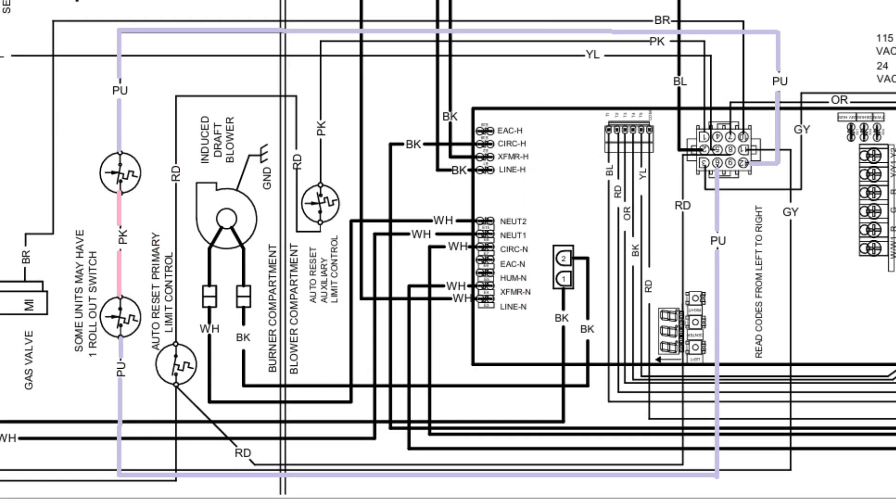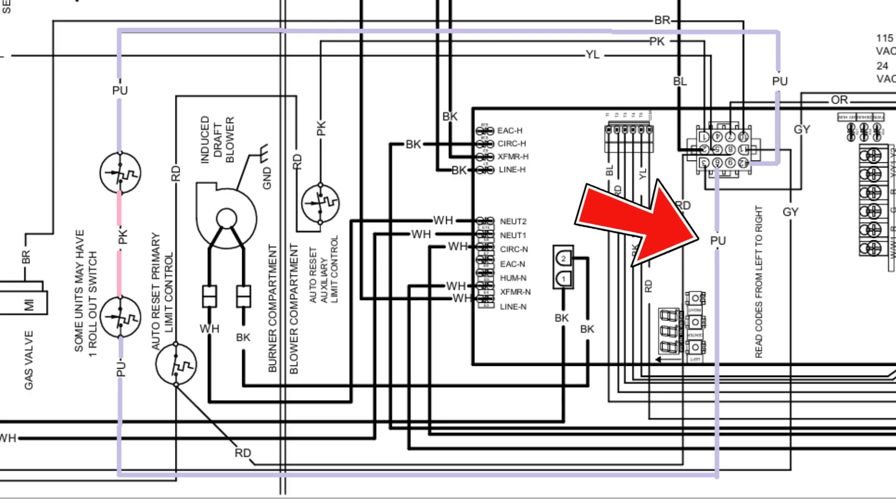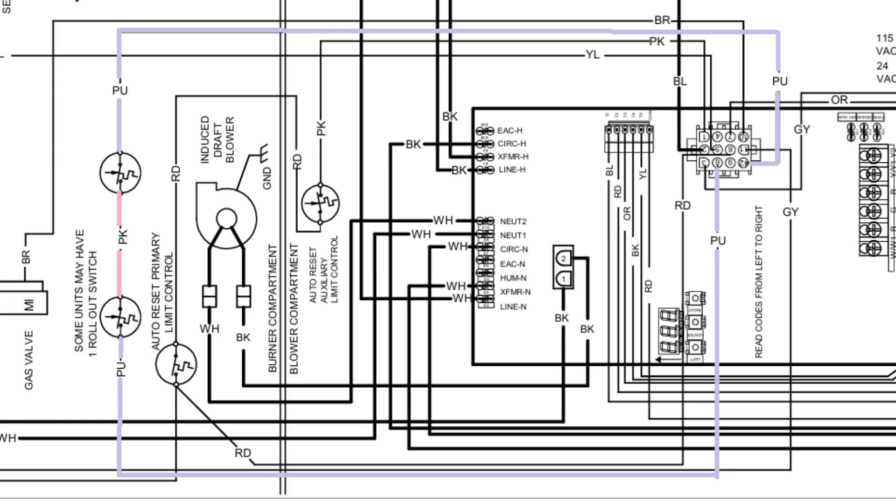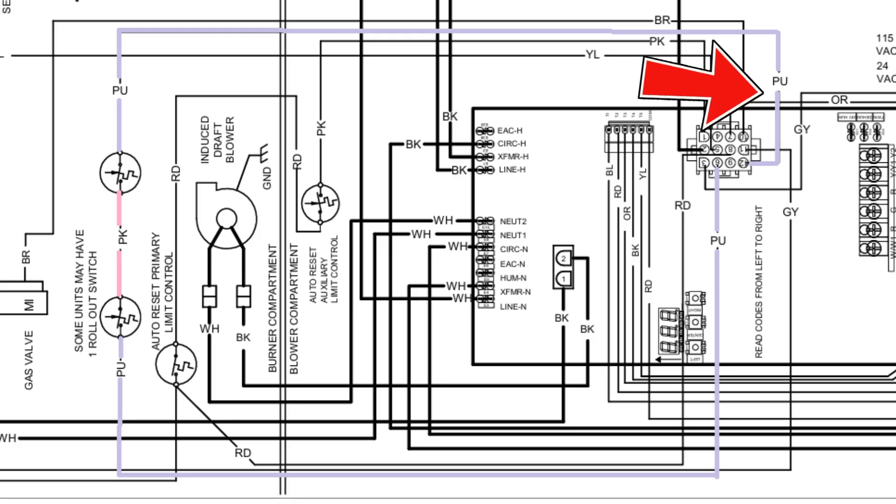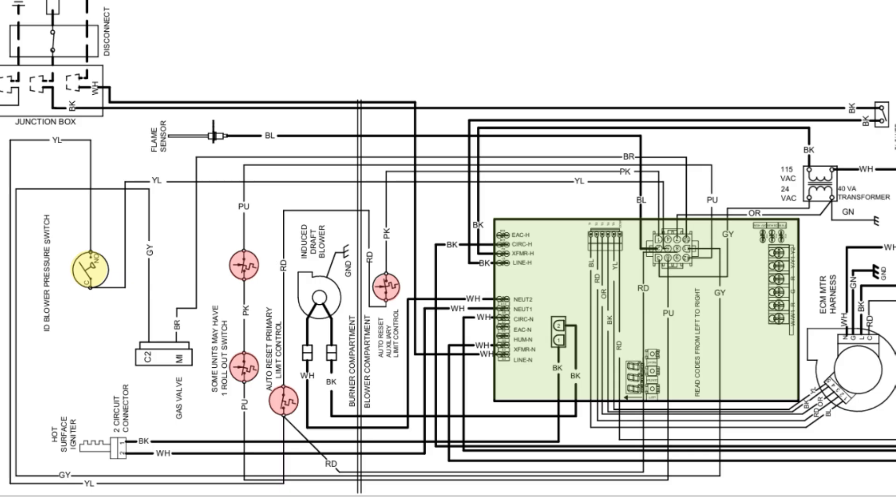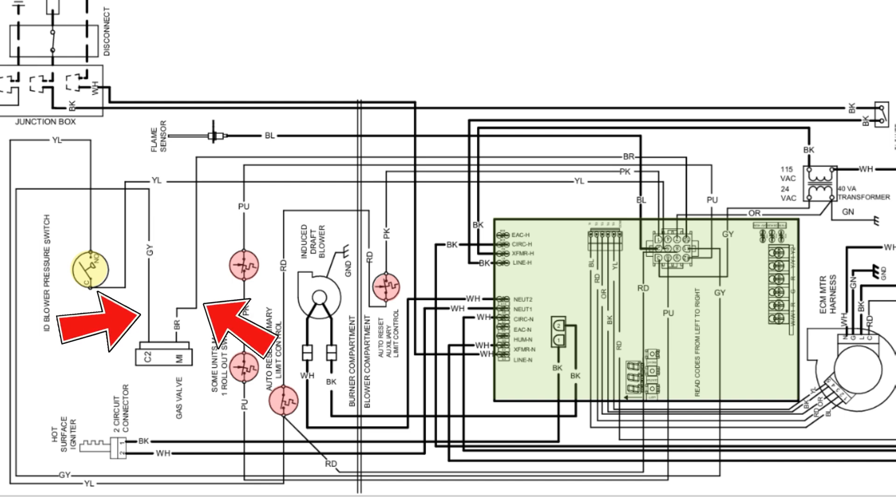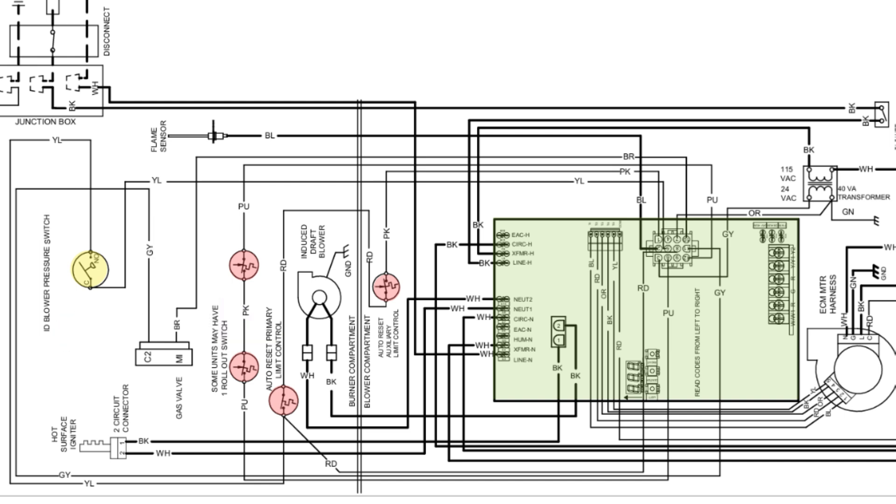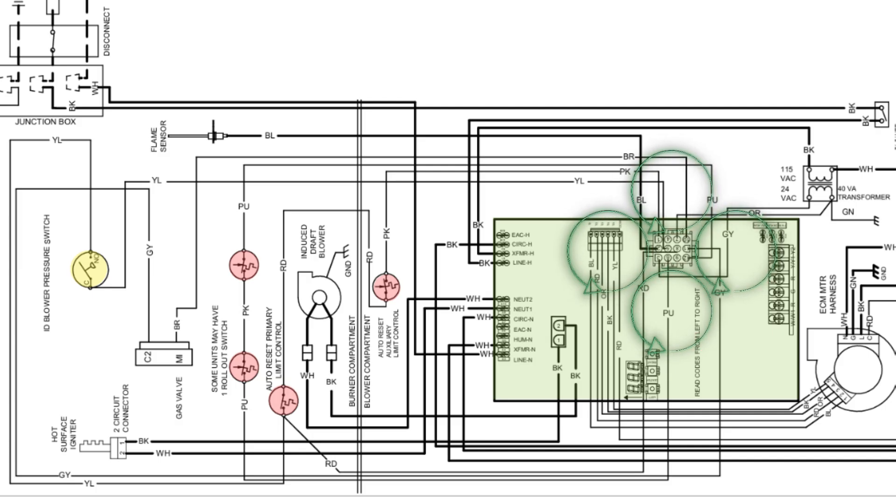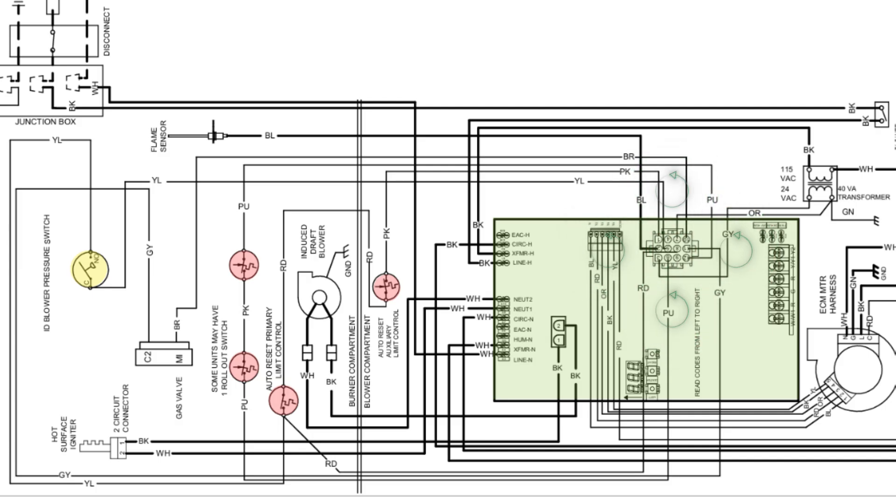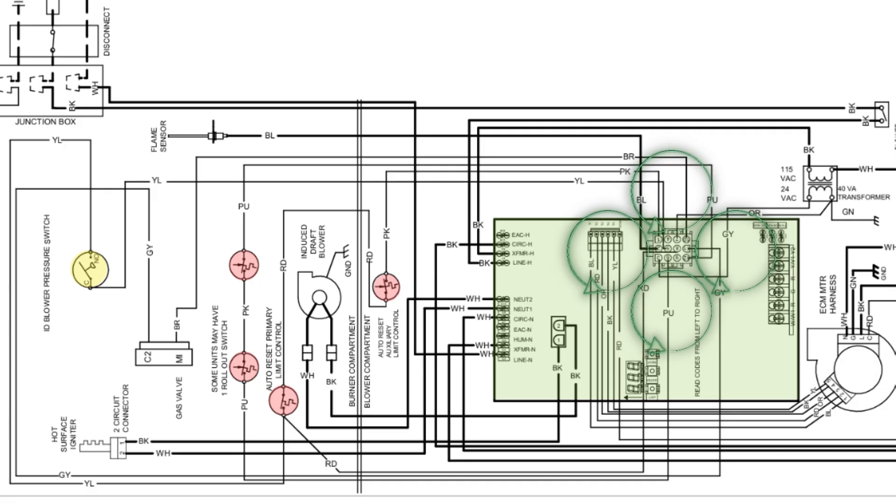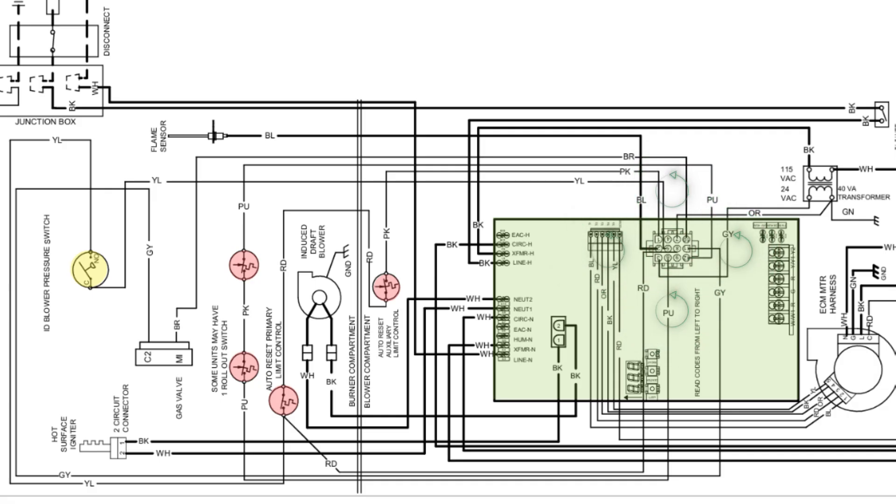Then maybe you see another purple wire coming off the Molex plug going through your flame rollouts, and then coming back on, in this case, another purple wire back to the Molex again. And same thing with a pressure switch, maybe a pair of yellow wires, and then you have one going to the gas valve and back. Everything leaving the Molex and coming back to the Molex. And this all definitely seems like the Molex plug is putting out 24 volts on each one of these loops, and each one's sending it back, and that sounds an awful lot like a parallel wiring setup.